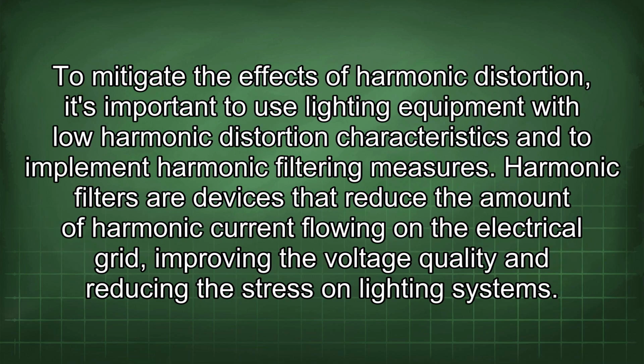To mitigate the effects of harmonic distortion, it's important to use lighting equipment with low harmonic distortion characteristics and to implement harmonic filtering measures. Harmonic filters are devices that reduce the amount of harmonic current flowing on the electrical grid, improving the voltage quality and reducing the stress on lighting systems.